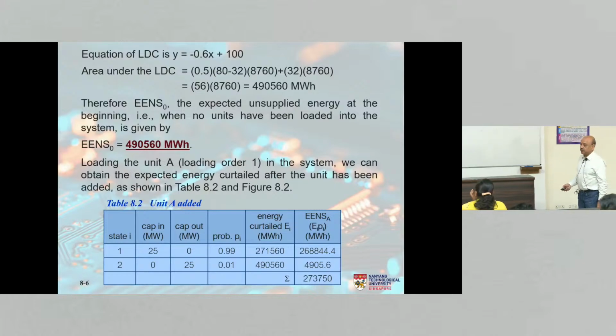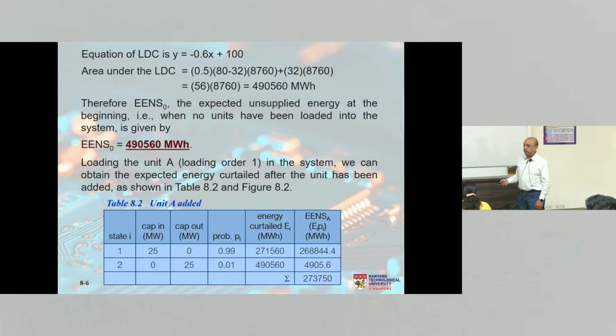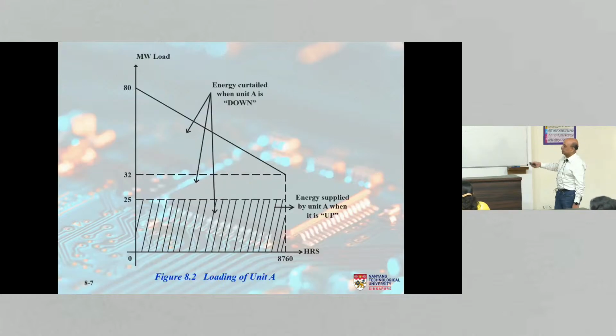So in our case, we have a straight line from the 100% to the 40% points, and the peak load is 80. So you can find the equation of the straight line, y is equal to mx plus c, and this is how it turns out to be. Now what is the area under the load duration curve? If you look at this graph, this is the time 0 to 8760. This is the load in megawatt. The peak load is 80, the lowest load is 32, right? 40%, correct? The load varies from 100% to the 40% point as a straight line, and the peak load is 80 megawatt. So it varies from 80 to 32, correct? So the equation of the straight line is y equals minus 0.6x plus 100.